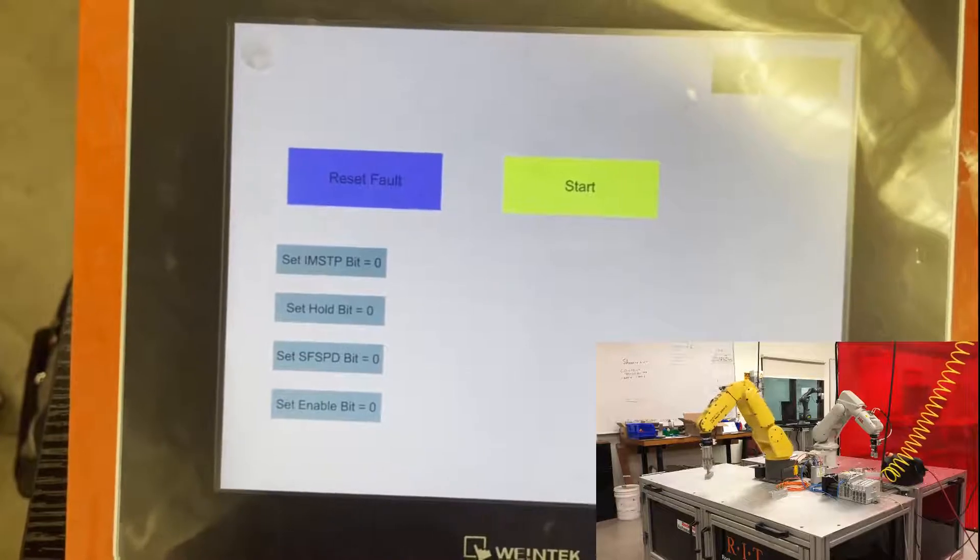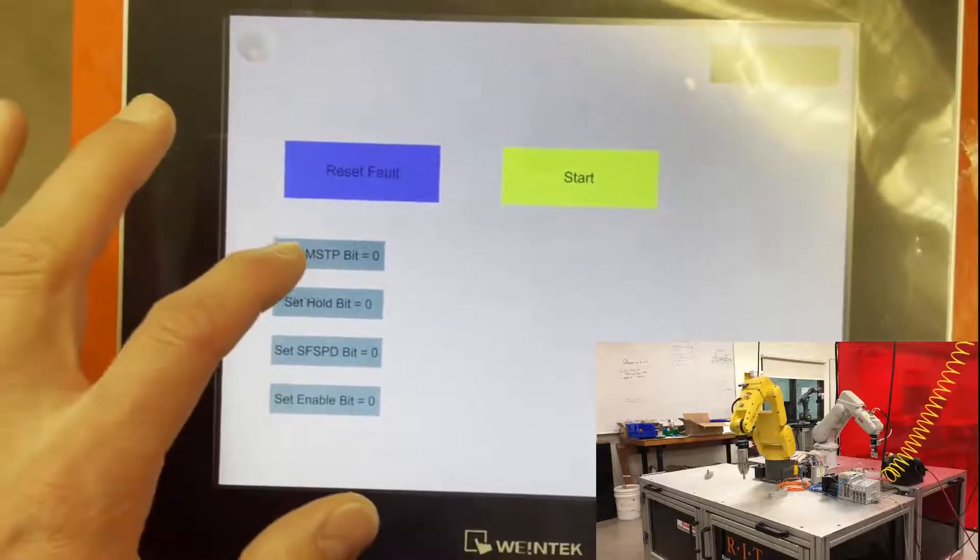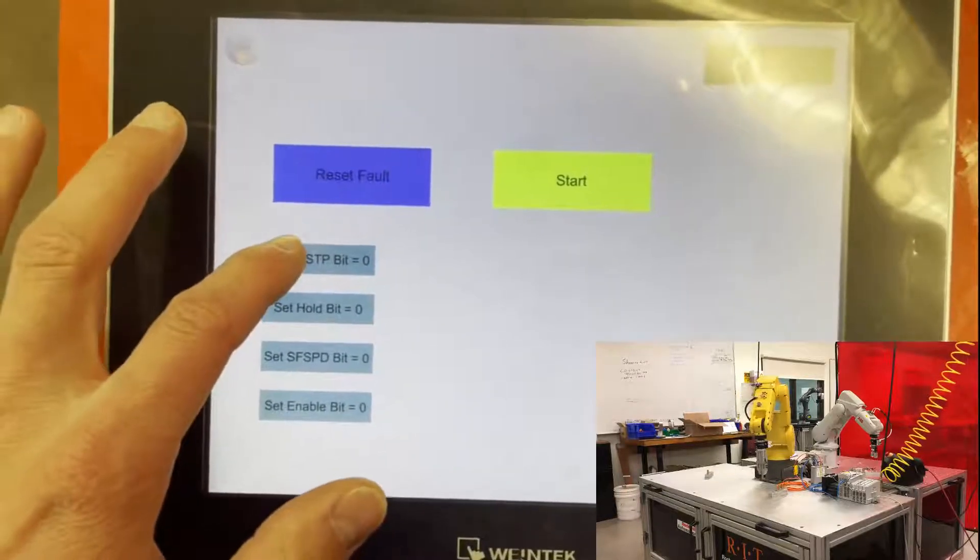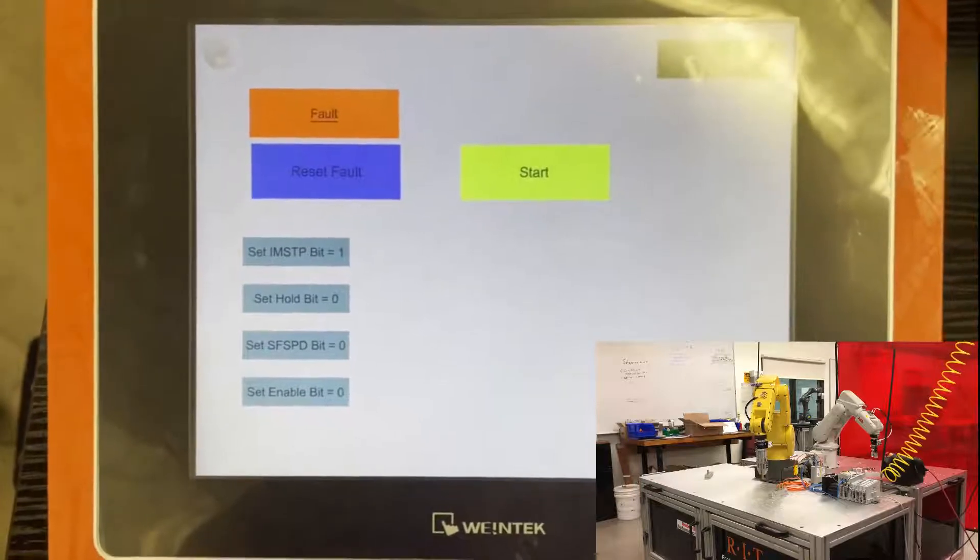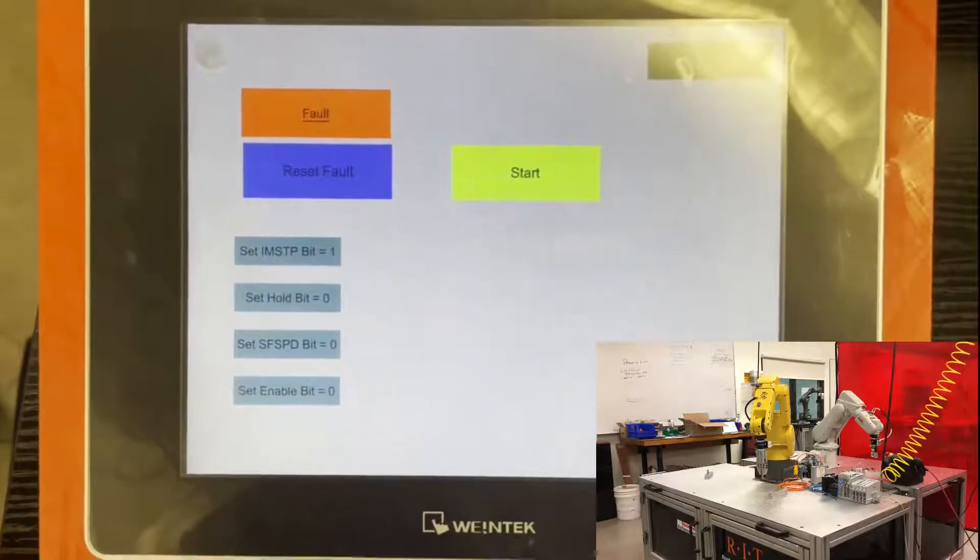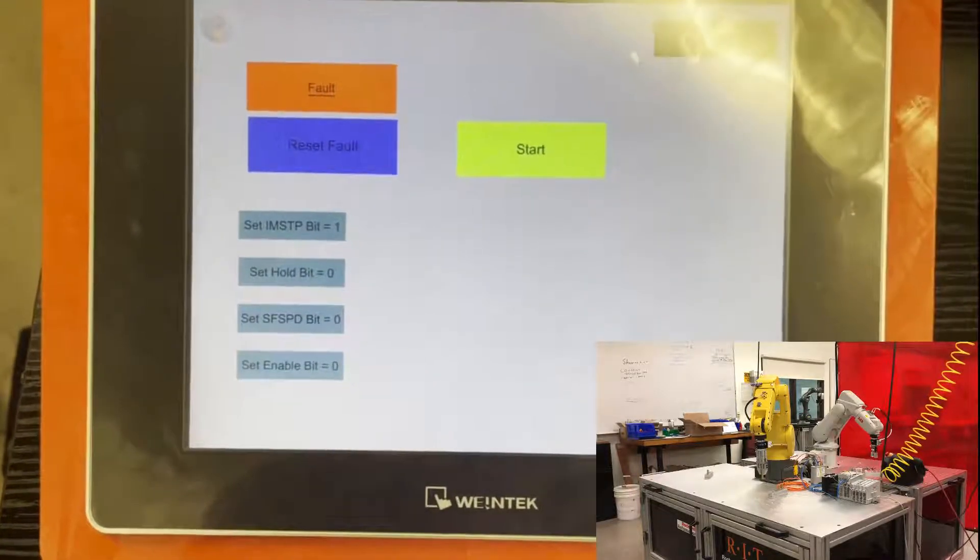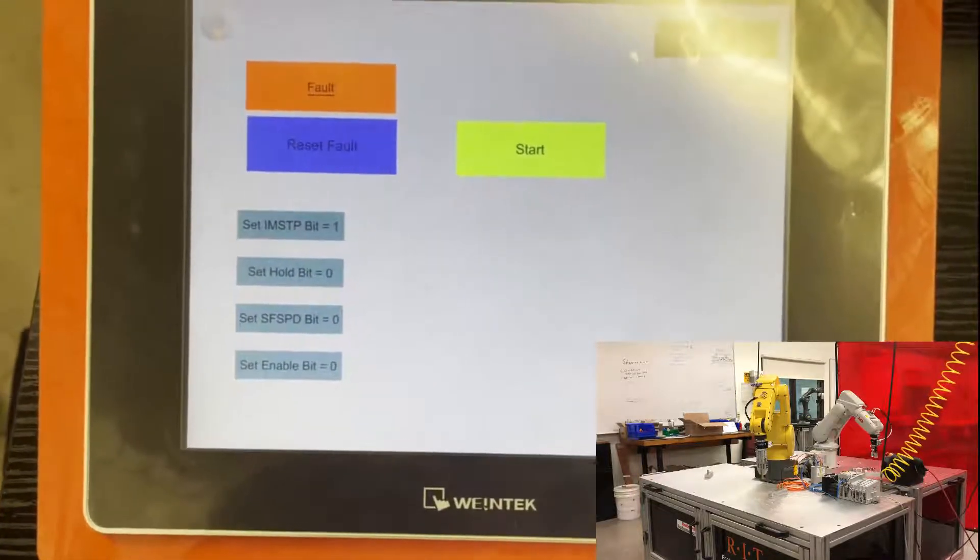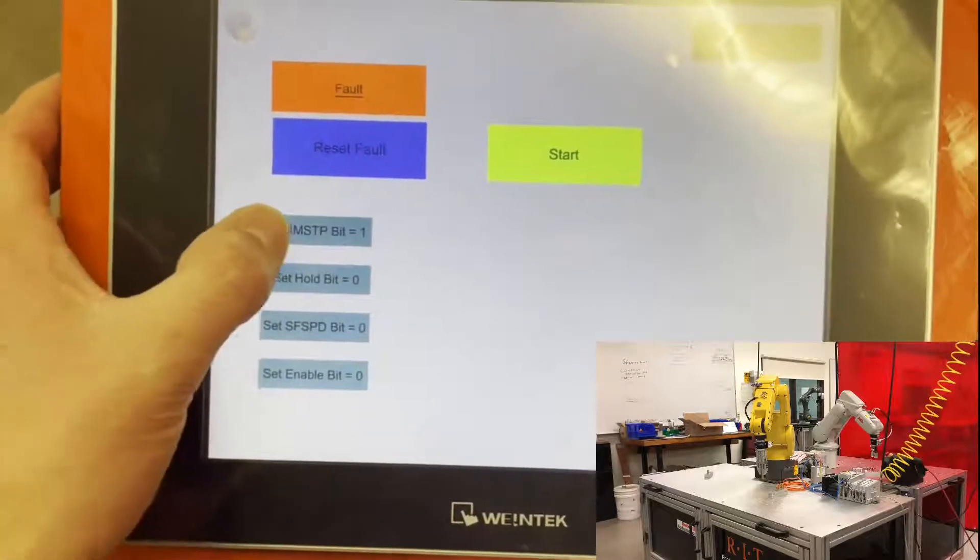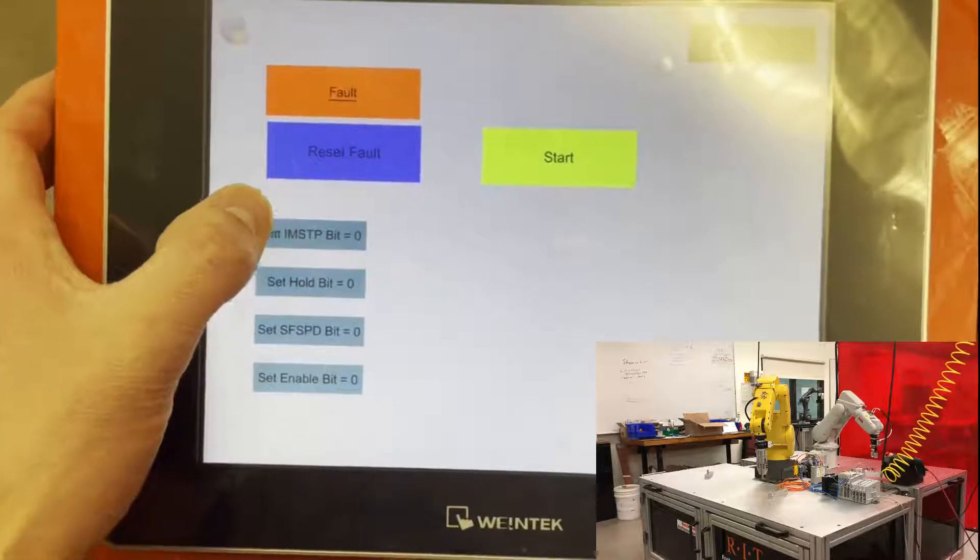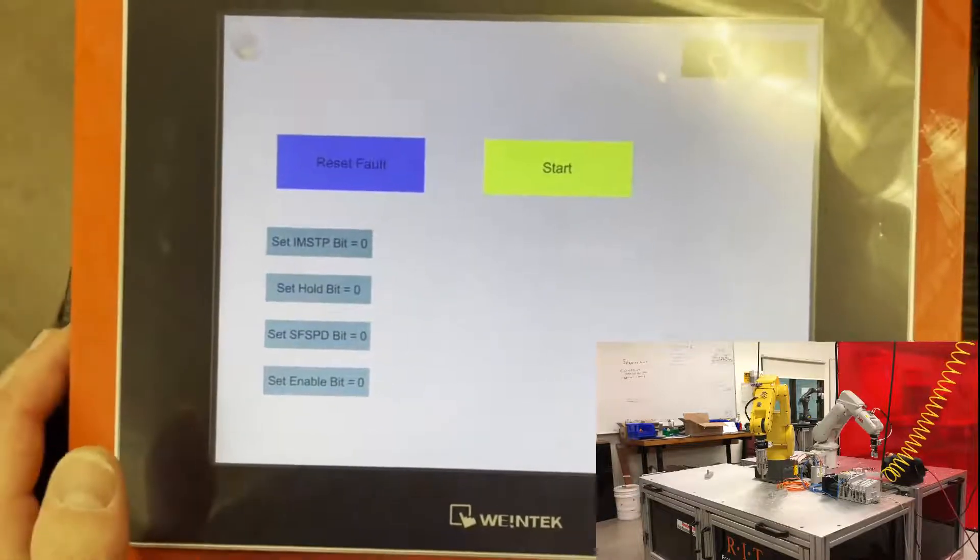The IMSTP bit, this is used to fault the robot. So as you can see, you can use a sensor to trigger that bit if a door latch is broken or anything like that. Then this bit needs to be reset to zero in order for faults to be reset.